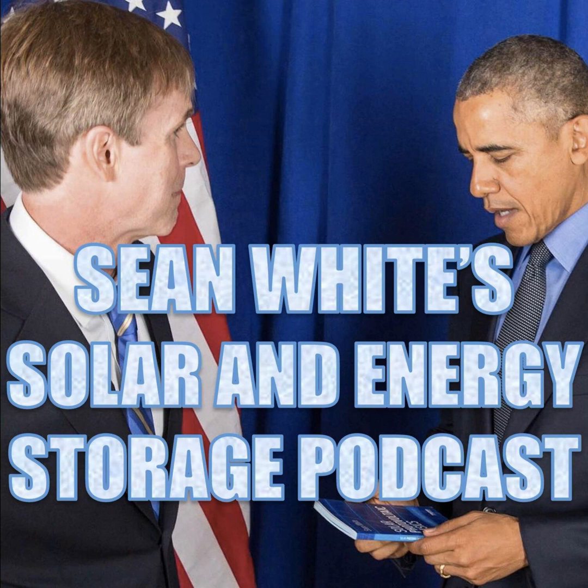And then battery locations. So we need to have ventilation appropriate for battery technology. It used to be that it just said that we had to have ventilation and people were required to ventilate even lithium batteries that don't put off gases. But if you have lead acid batteries, that's when you need ventilation. And lead acid batteries, as lithium gets cheaper, lead acid is going more and more out of style. Some people thought we would never get here, folks, but lithium is getting cheap.